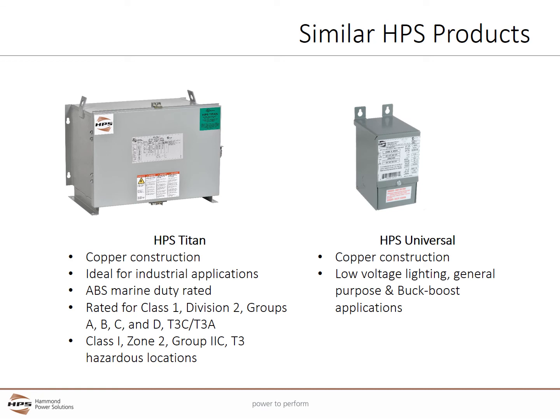HPS offers other encapsulated transformers for a variety of applications. The HPS Titan series is suitable for industrial hazardous locations and is rated for Class 1, Div 2, Groups A, B, C, and D with a T3C and T3A surface temperature rating, and Class 1, Zone 2, Group IIC hazardous locations with a T3 temperature rating. Titan also comes standard with an ABS marine duty rating, and the rugged hinged enclosure on the 3-phase units provides industry-leading flexible installation options.